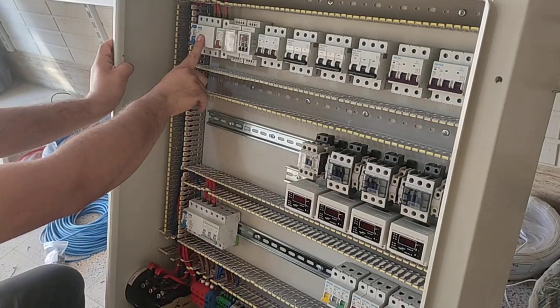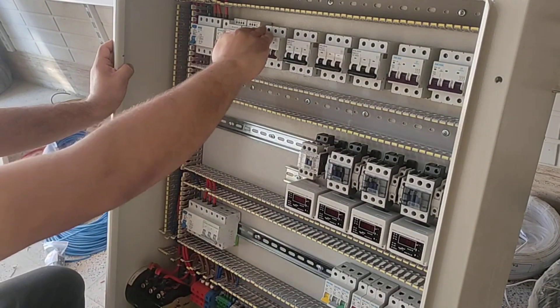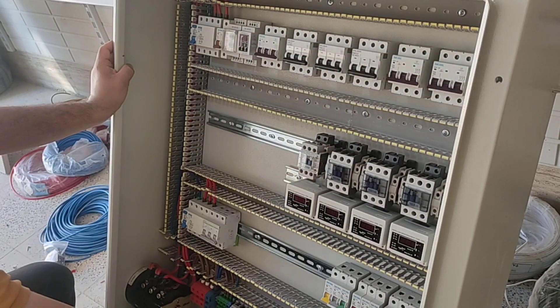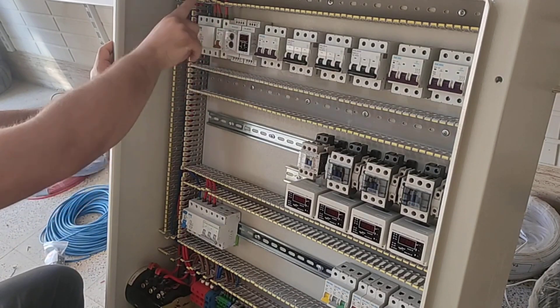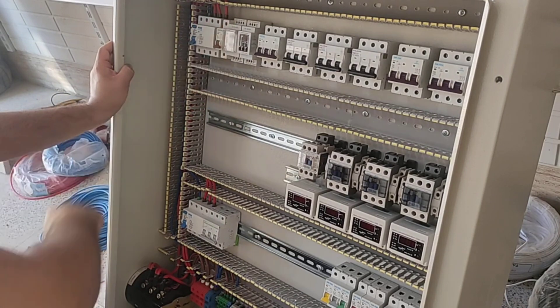Now we connect the output of the RCCB switch to all the inputs of the three-phase and single-phase miniature switches. We also connect one sample of each phase to the three-phase monitoring relay so that the voltage of the phases can be controlled.